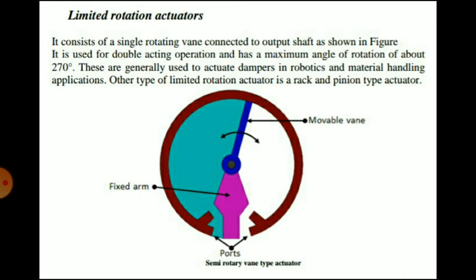Limited rotation actuators consist of a single rotating vane connected to an output shaft, with a movable vane, a fixed arm, and two ports. They are used for double-acting operation and have a maximum angle of rotation of about 270 degrees. They are generally used to actuate dampers in robotics and material handling applications. Another type of limited rotation actuator is the rack and pinion type actuator.